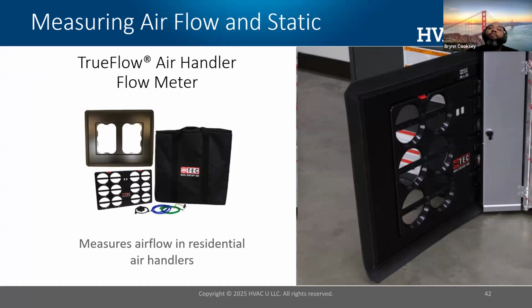One of the things we do, we measure for airflow of the existing system to see that heat pumps are actually feasible in this location. And two things need to be true. Do I have a building shell that can accommodate a heat pump correctly? And do I have a duct system that I can measure, get the airflow requirements of the duct system, measure static pressure or bursting pressure of the duct system to see if a heat pump is the ideal candidate? Again, heat pumps are wonderful and they work everywhere, but there's a little bit more homework we have to do to have rapid heat pump adoption.